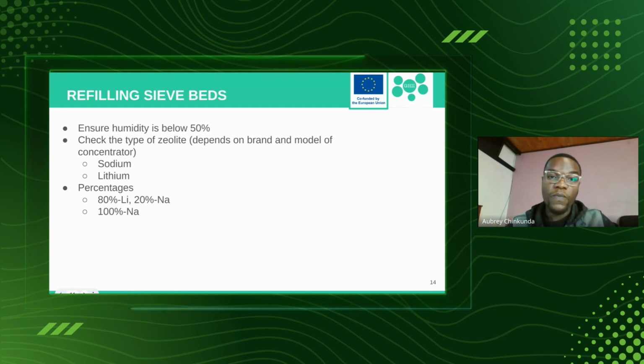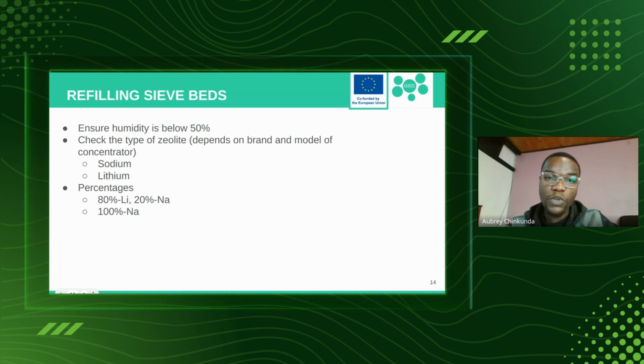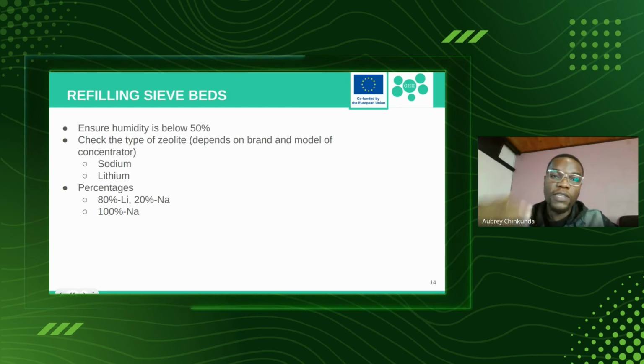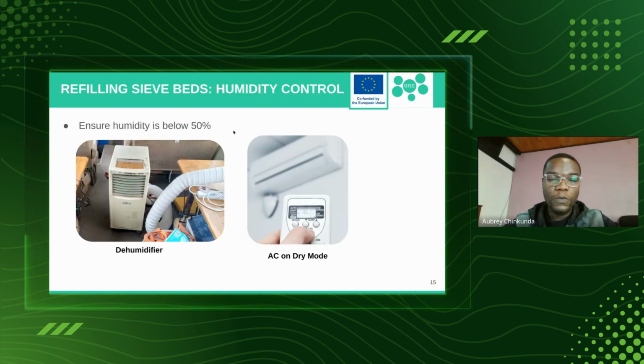The way we refill here, some concentrators use 100% lithium, others we mix lithium and sodium, mainly because lithium is more efficient but also easily damaged by moisture. To protect it, some put a desiccant at the bottom where air comes from the compressor, to absorb moisture before the adsorption process. Others put a layer of sodium zeolite because it doesn't absorb moisture at as high a rate as lithium. So we put 20% sodium and then lithium after that, to protect that layer of lithium zeolite.